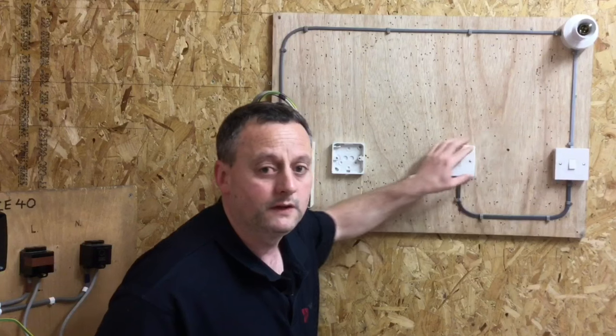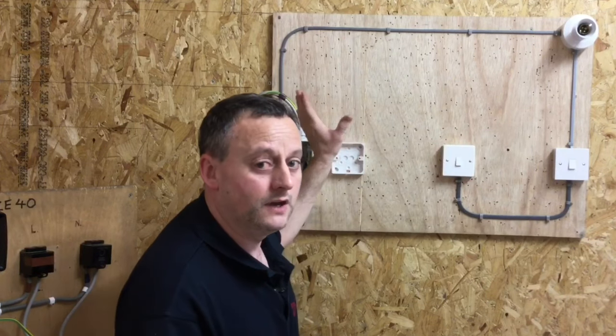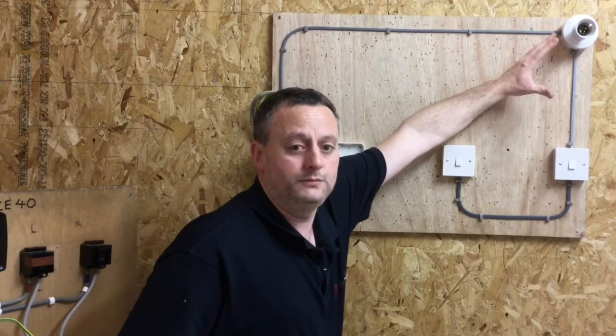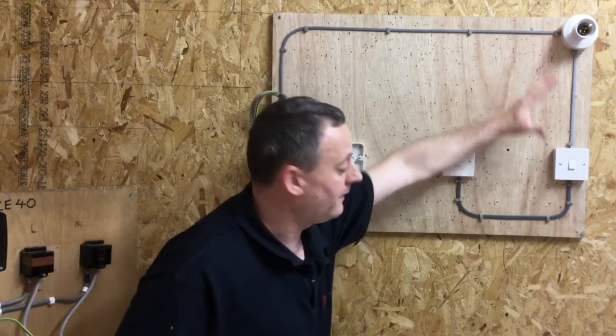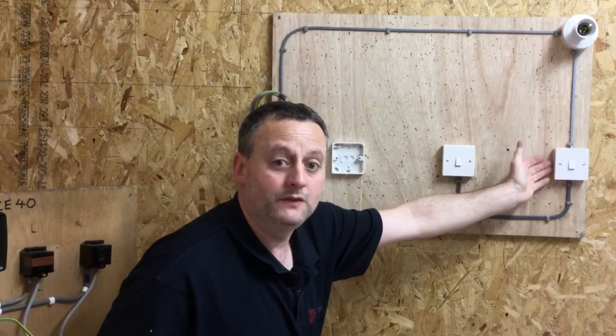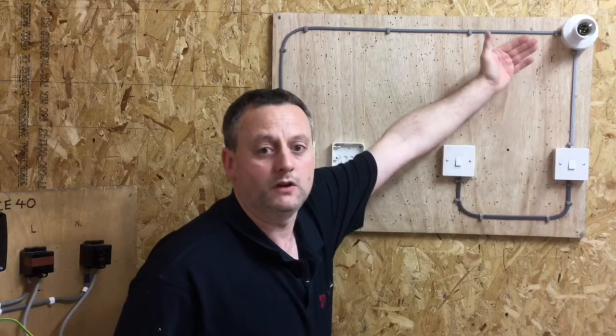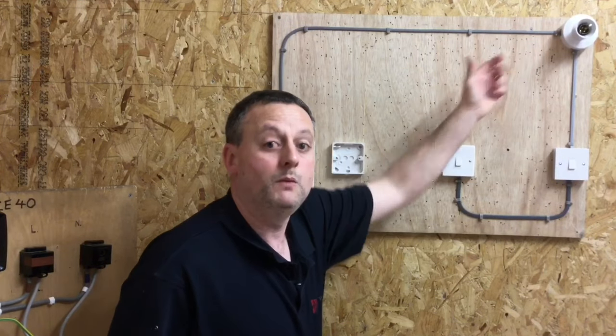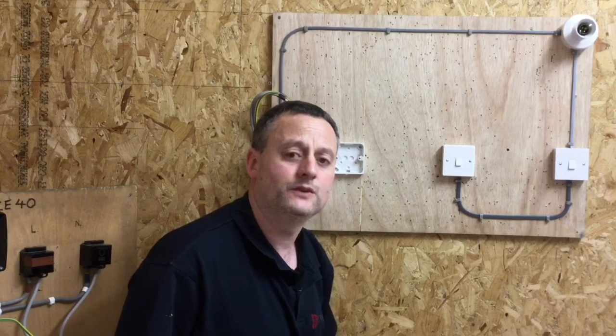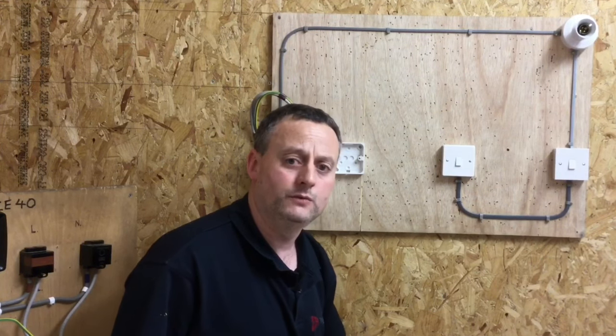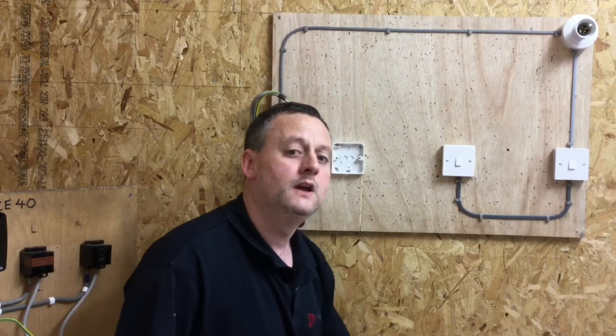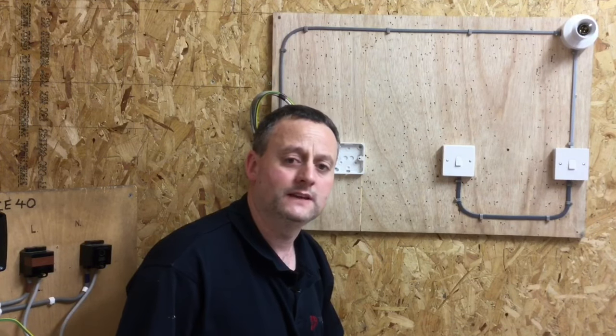That goes off, that goes on. The circuit line now comes up into the loop terminal, down on our twin brown, now down the grey strapper, through round the black common, and turns on our light fitting. So we repeat the insulation resistance test at the distribution board or consumer's unit again for the second time. Walk around the installation throwing all the two-way switches into the opposite on position, return to the board, and repeat the insulation resistance test.